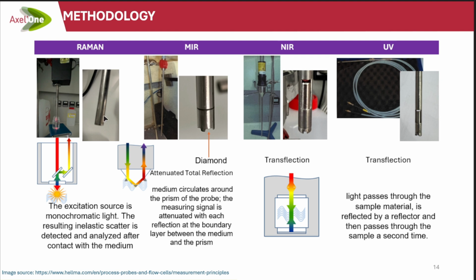For Raman, Raman is a system where you have inelastic diffusion of the photons that you are collecting. So you can actually send the light through the probe and collect it from the same window as a backscattering. You're only collecting signals, but it's usually enough if you collect it right. And so it's a very flat system. The MIR probe is an ATR, attenuated total reflection system. So you have a crystal on which you do the measurements, and this measurement is really done at the surface of your probe. So you have to have a good renewal of your product every time at the surface of your probe.